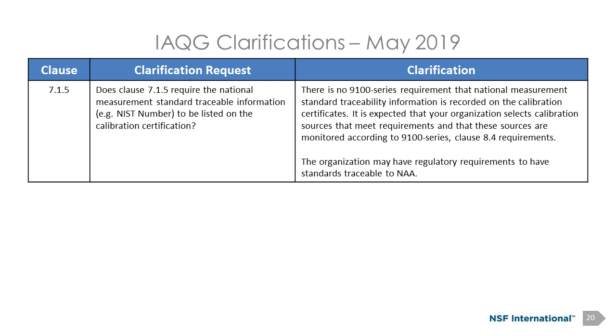We need to be able to show that it's done at this lab. We need to be able to show that it used these serial numbers, but we don't need to necessarily show the national measurement standards traceability information. So it doesn't have to go back to that NIST asset. We just need to be able to see the trace back to whatever that third party's process is. And I've seen plenty of certs that say they don't have tools listed. They just say it's this certificate number, and if you want more, give us a call. That's perfectly fine because there's a linkage from that certificate back to their process, to their methodology, and to their records and retained documented information.